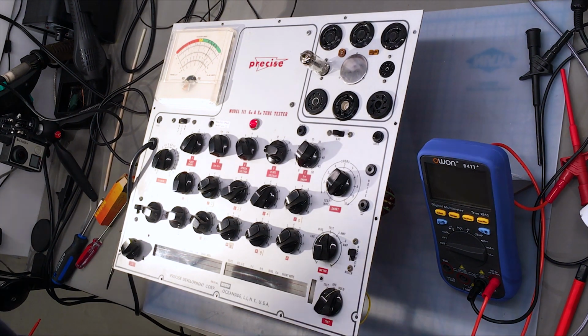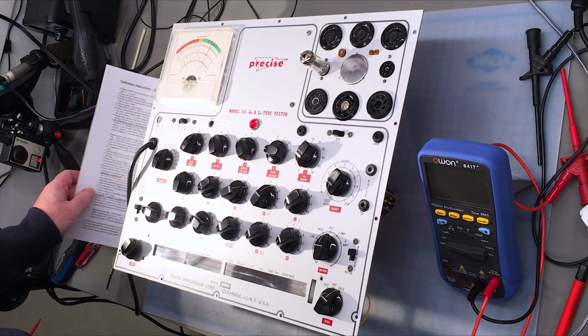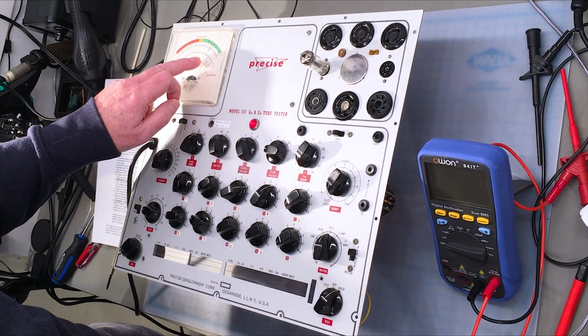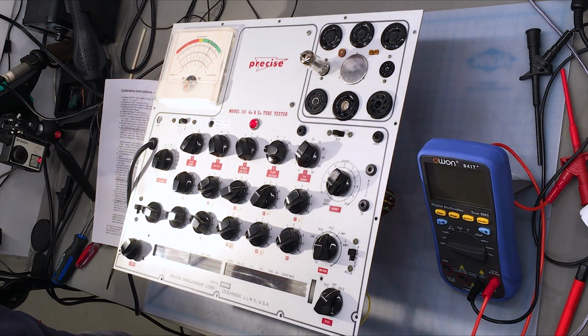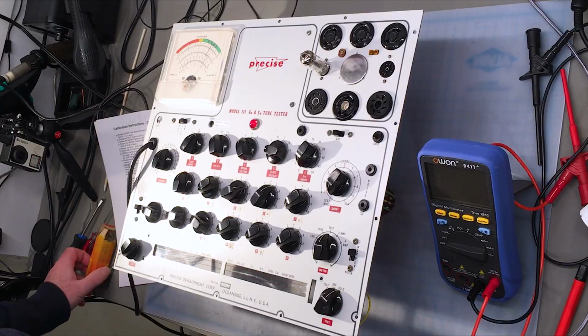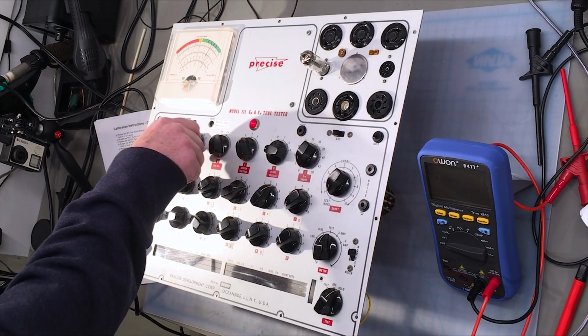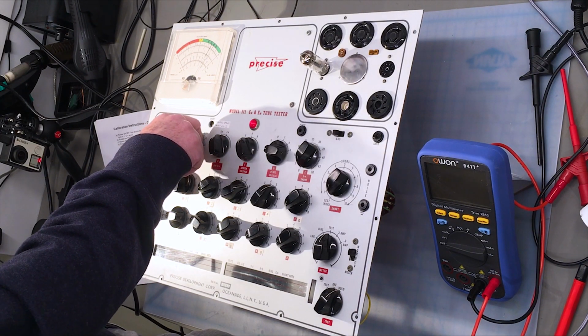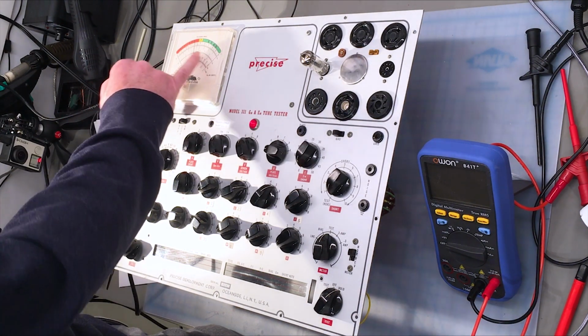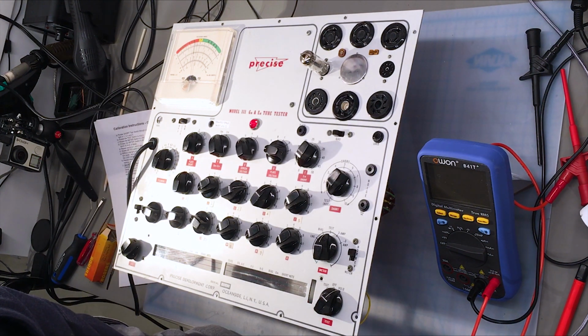We rotate the meter test switch to test and note the reading on the 3000 GM scale. That scale is right here, and we have a reading of approximately 2,380. Then we rotate this switch to the 6K setting, which means the meter is now reading GM on a different scale, and we're hoping to have the same reading.